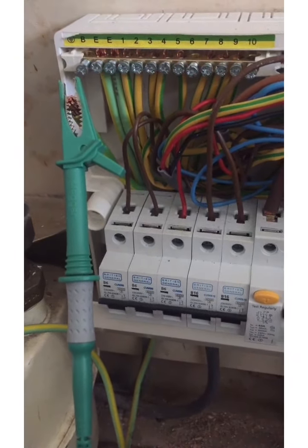there's the value that I got previously on the meter, 0.23 ohms. Now let's see if we can duplicate that. With these tests, they can jump around a little bit. So with these one-shot tests, you're probably best not to make them a one-shot, or maybe take a second confirmation. So let's see if we get that value again.